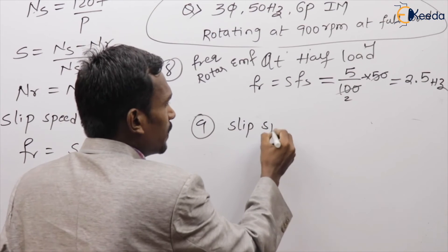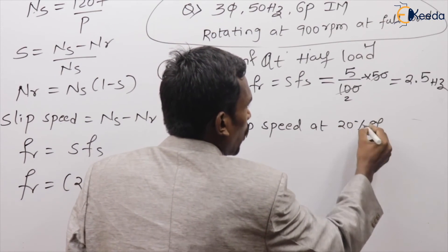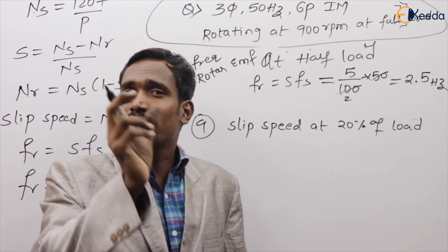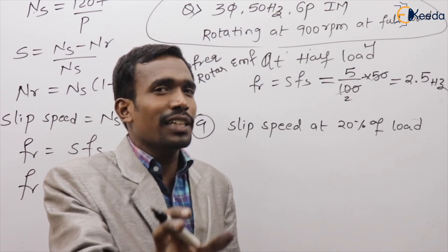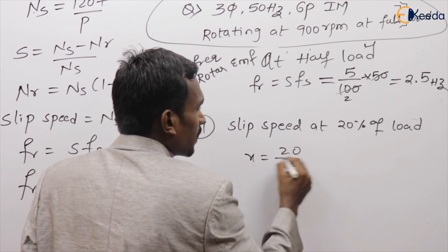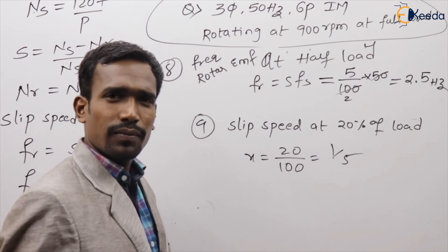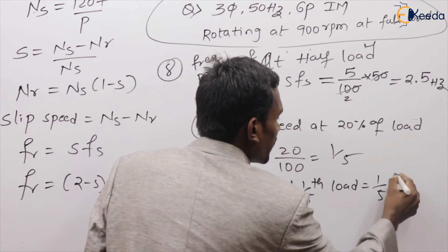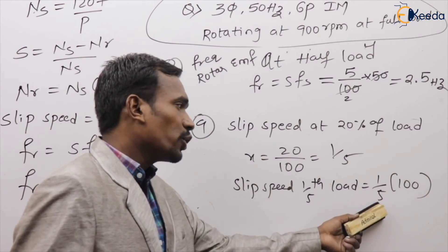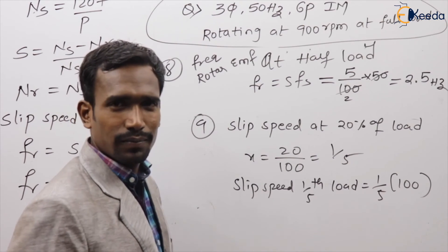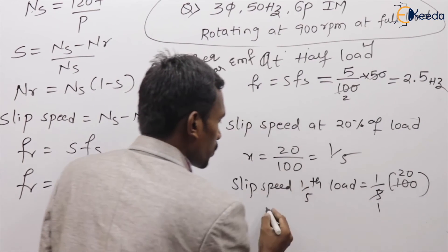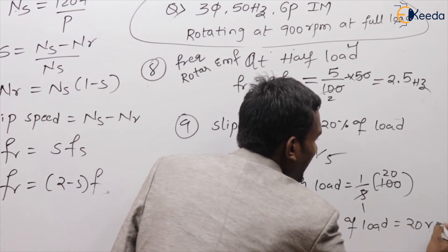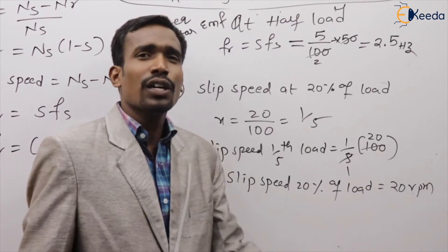Ninth question: what is the slip speed at 20% of load? The Xth load slip speed equals X into full load slip speed. Here X is 20% which is 1/5, and full load slip speed is 100 RPM. So slip speed at 20% load equals 1/5 into 100 equals 20 RPM.